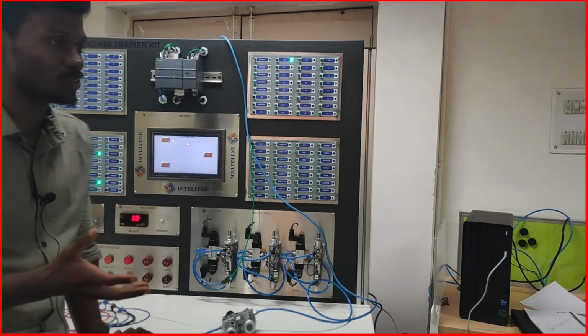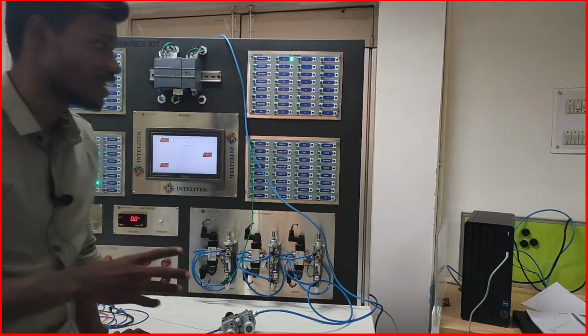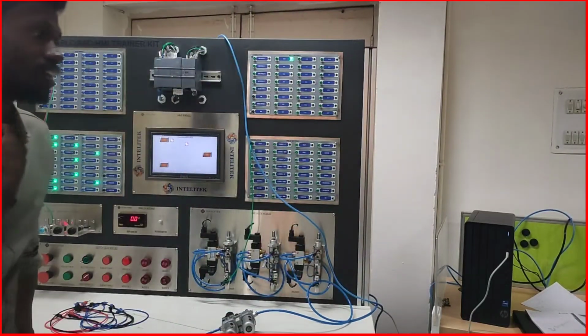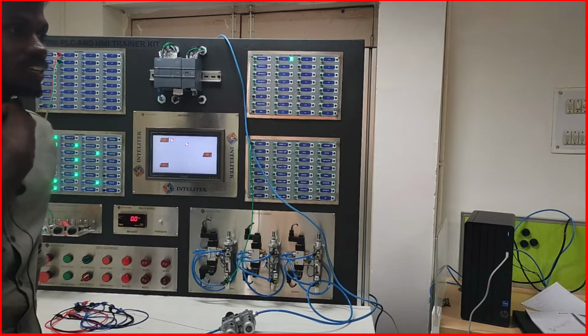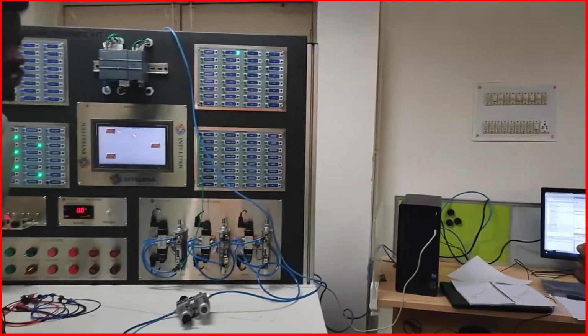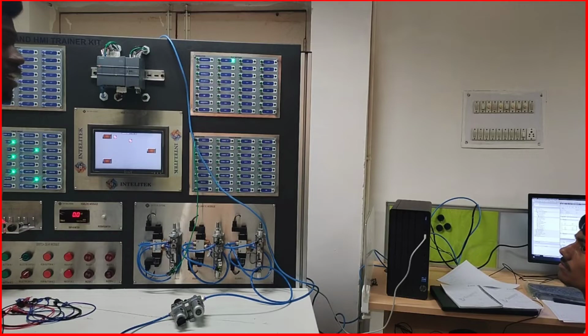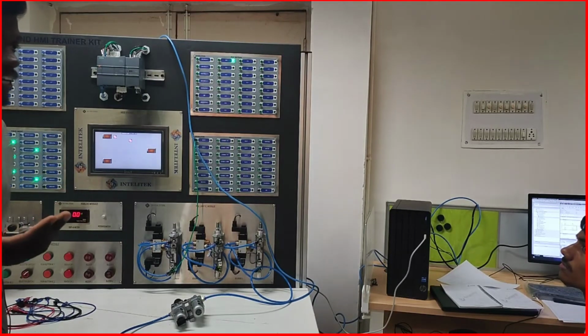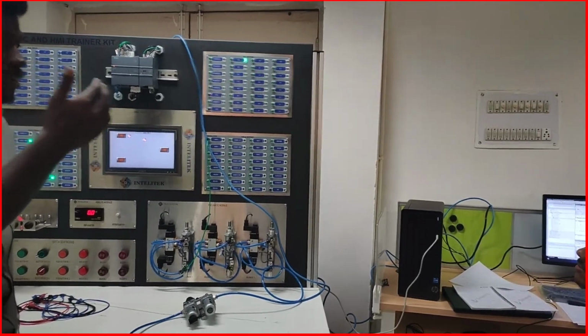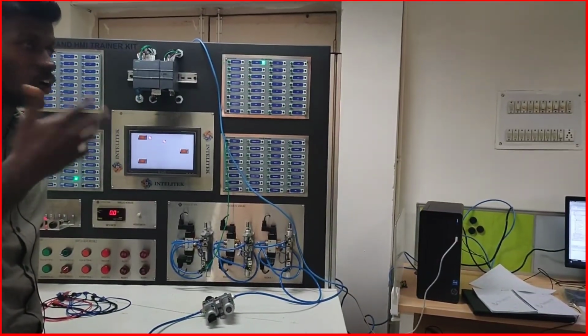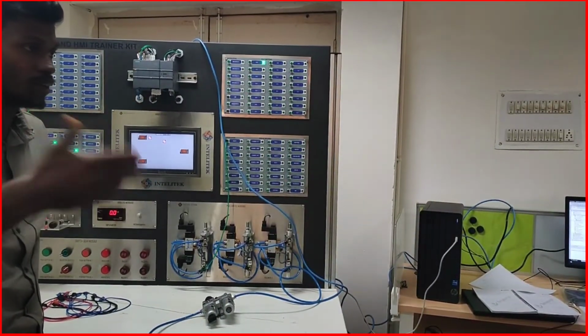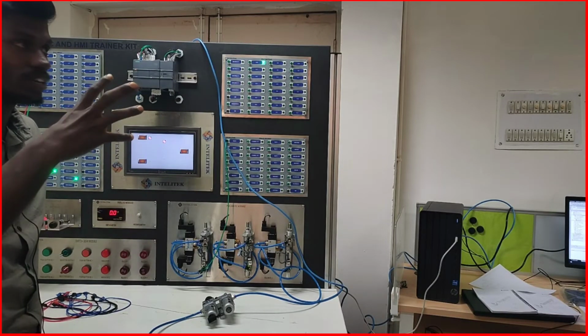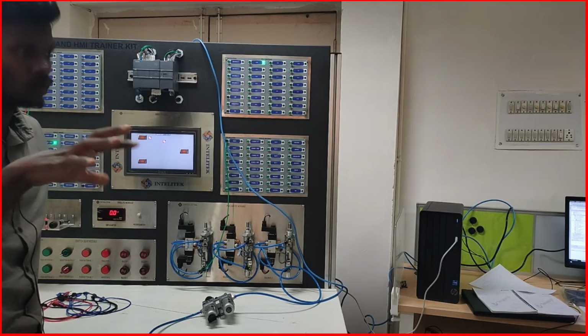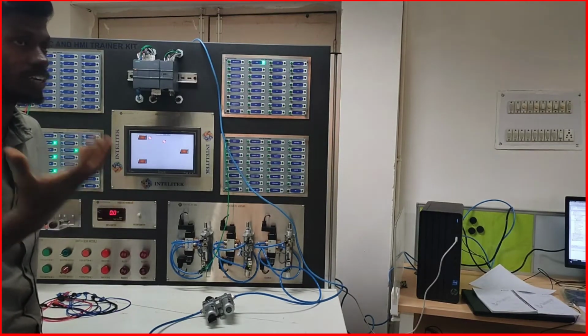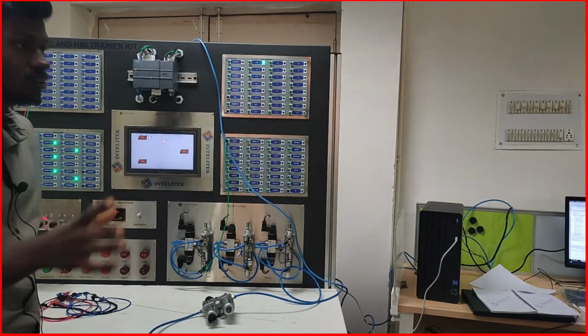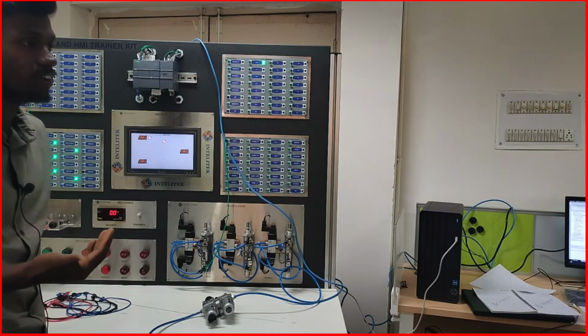This is how the controllers also work, same DDC controllers, so PLC controllers. As per these gates, how they work is they set a temperature, and if they sense the room temperature should be 50, the controllers, once it exceeds 50 degrees, will turn off the heater or fan, whatever hot air is coming should be closed. At that time they will turn on some other cooler to cool the room temperature. To control and maintain room temperature, we use these controllers. Like this, we have to build applications.